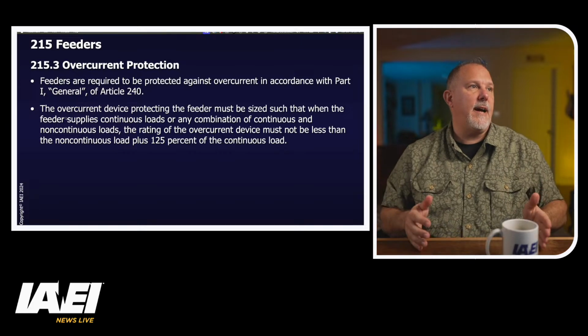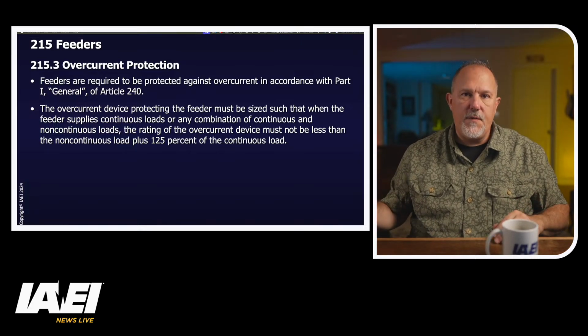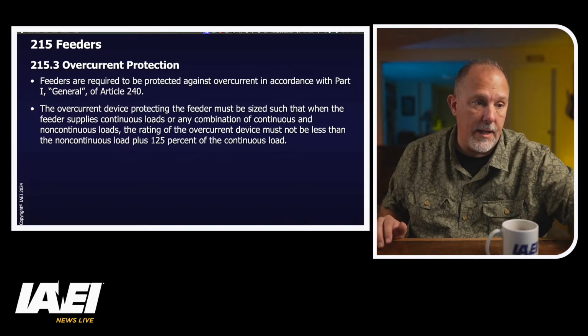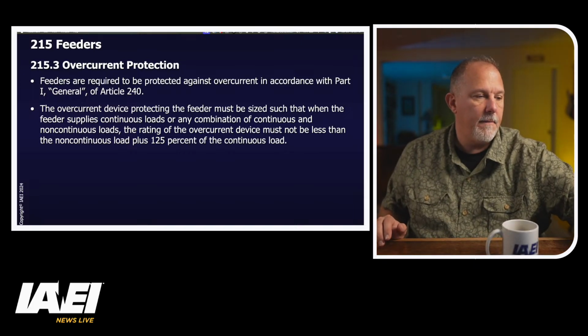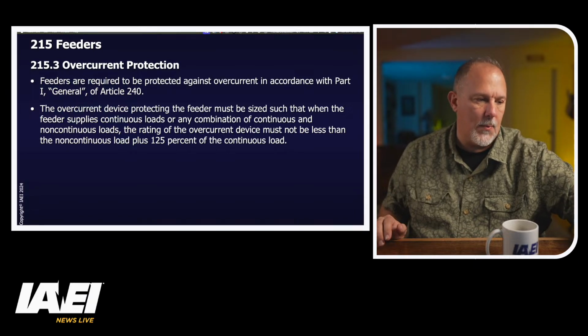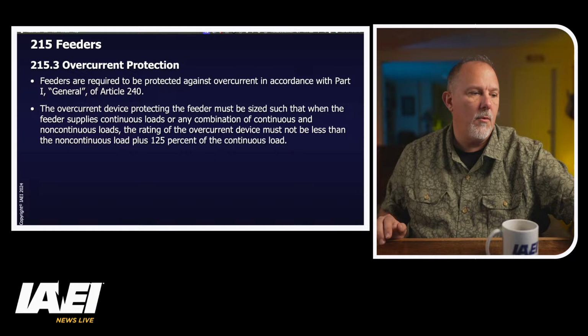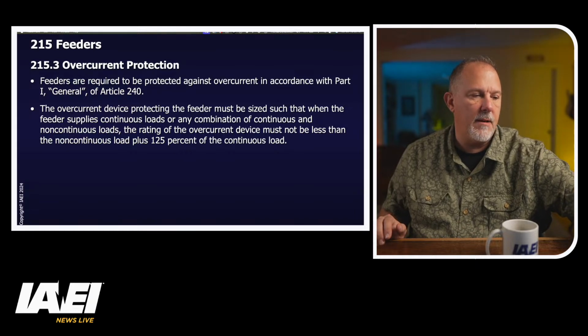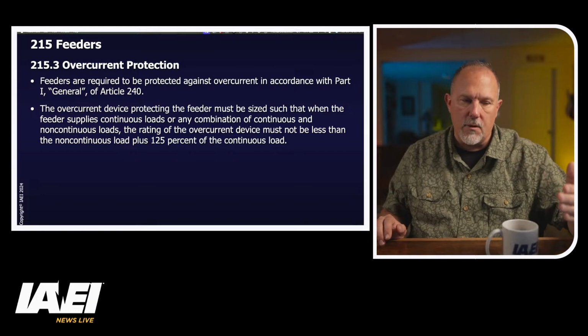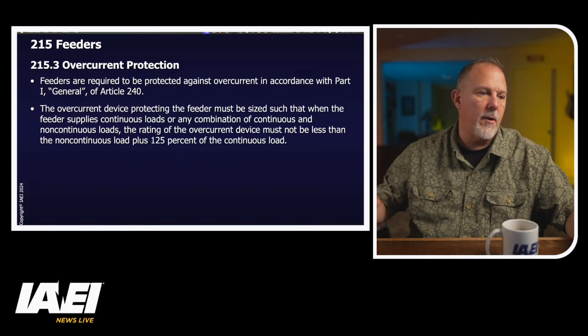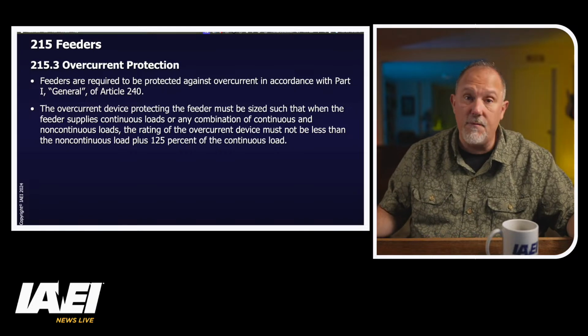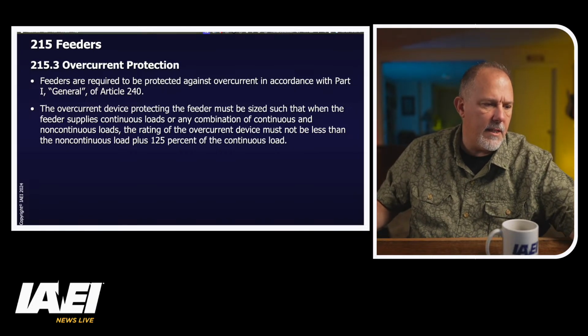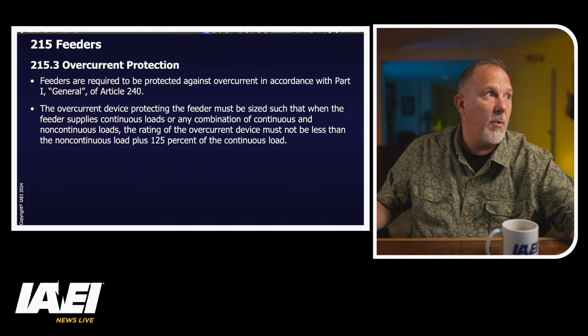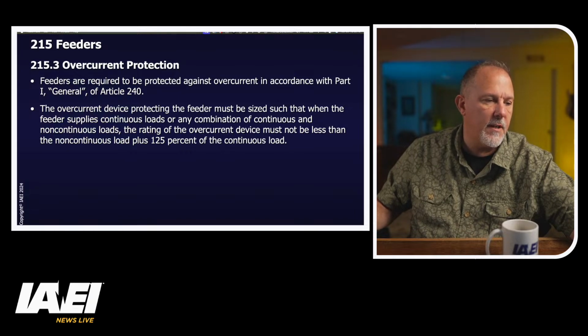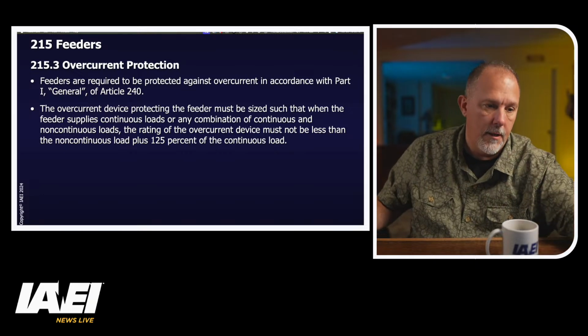215.3 just tells us that I have to protect those feeders based upon Article 240. And now this, and I'm torn on this one. It says Part 1 general requirements. I have to protect this based on Part 1 general requirements. In Part 1 of Article 240, you have your scope, you have your reconditioned equipment, you have other articles, you have your protection of conductors, 240.4. So it's Part 1. So that would mean protection of conductors is in 240.4.